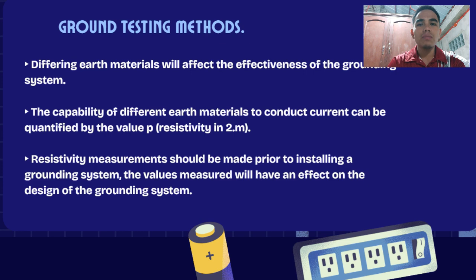So, ground testing methods. Differing earth materials will affect the effectiveness of the grounding system. The capability of different earth materials to conduct current can be quantified by the value rho, resistivity in ohm-meters. Resistivity measurement should be made prior to installing a grounding system. The value measured will have an effect on the design of the grounding system.